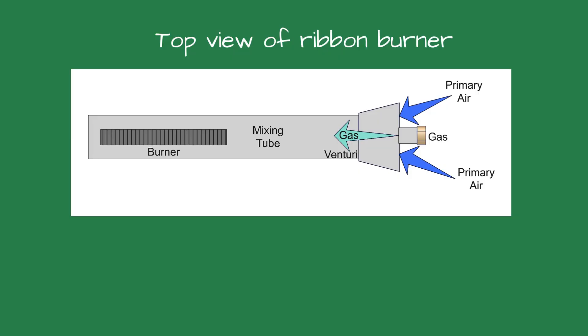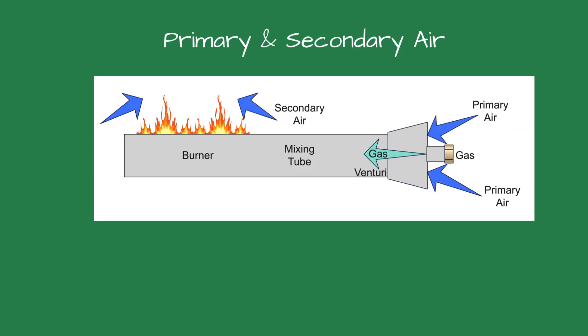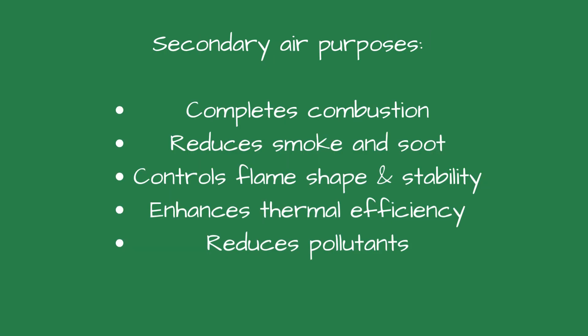On an atmospheric burner, the gas is sent through an orifice. The gas pressure is higher than the surrounding atmospheric pressure, causing a venturi effect and pulling in the primary air for the burner. When the flame is lit, the secondary air is mixed in with the flame and above it. The secondary air has several purposes — it provides extra oxygen to burn any remaining unburned fuel or carbon particles.